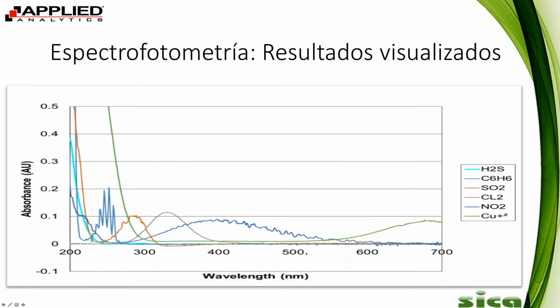You also get the full spectrum here. Like you can see, you get a measurement from 200 to, here only shows 700. We go up to 800. And having the full spectrum analysis, as opposed to, say, a photometer, which is a more traditional, simpler technology where you only get one wavelength. With the spectrometer, you get the full spectrum, so you get data at every single wavelength integer. What that does is it gives you flexibility in calibration. It gives you the ability to add a measurement in the field. So say you had an analyzer out there measuring SO2 and you wanted to add an H2S measurement to it, you could do that. You could calibrate for that because you're already measuring in the full spectrum.